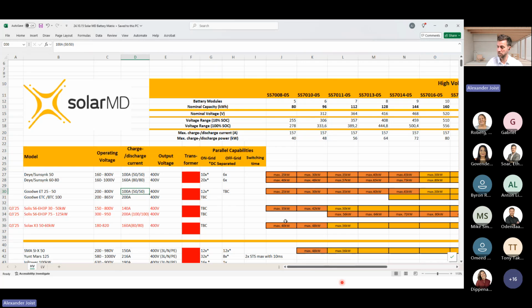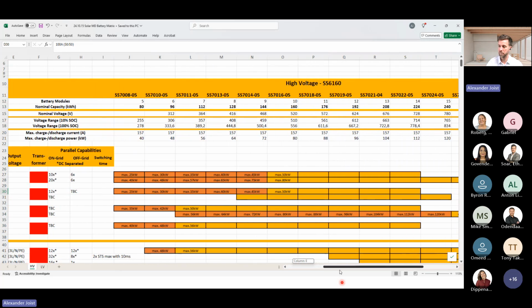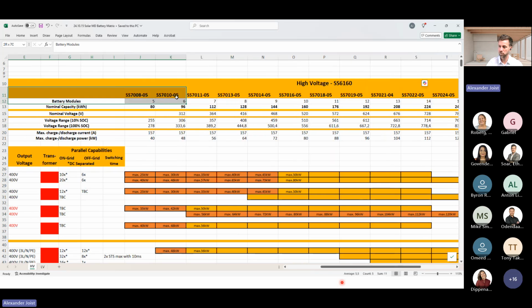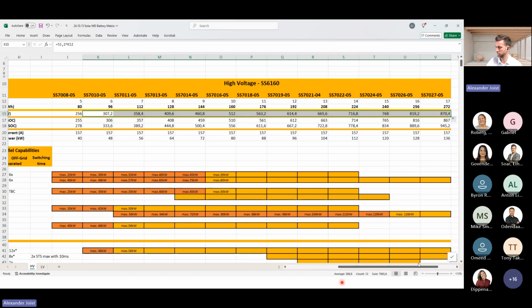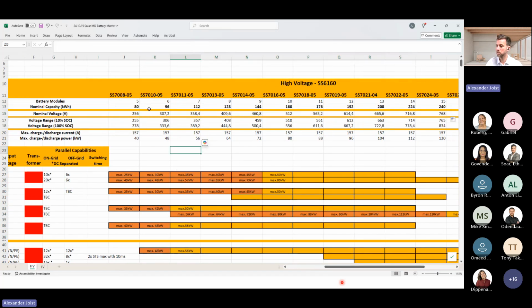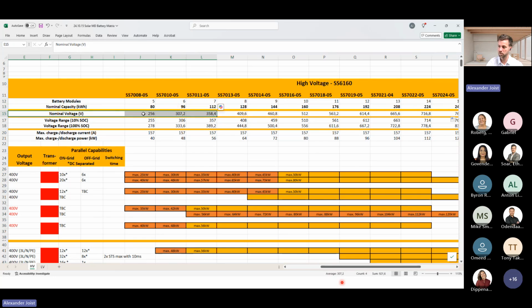So what does that mean? Now, in this table, we have all our batteries listed up here. How many battery modules, how many kilowatt hours per battery system, the voltage. I made a mistake there yesterday. I'll repair it right away. Perfect, now it's correct. So now we know the nominal voltage of the battery, and our max charge and discharge current is 157 amps. And with this battery we have a maximum charge and discharge power of 40 kilowatt.